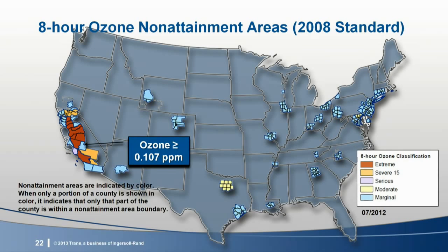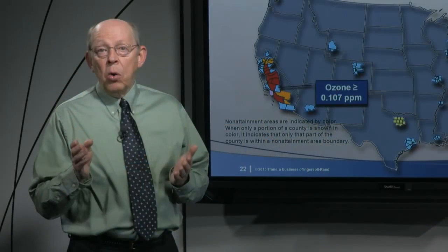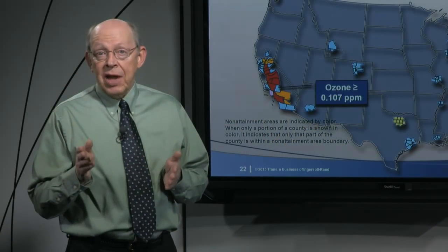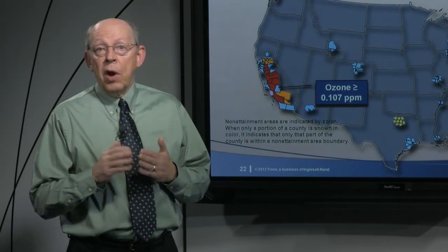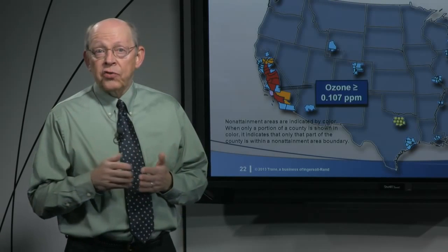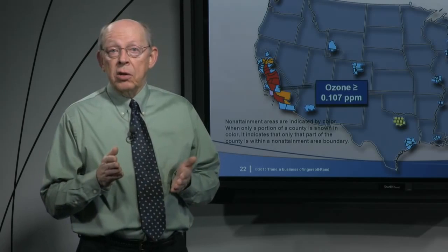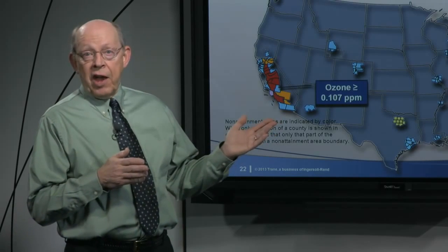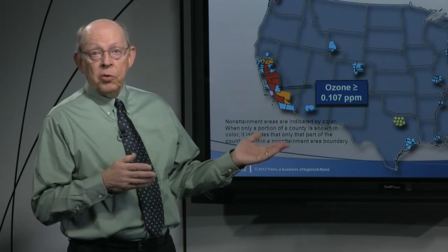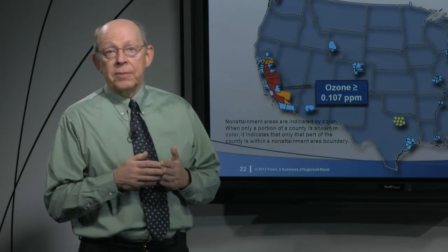Ozone non-attainment areas other than Southern California don't need air cleaners to meet Standard 62, but designers might want to consider using them anyway. After all, breathing ozone is harmful, and besides that, if you're designing a high-performance building, Standard 189.1 requires 40% efficient ozone air cleaners in all ozone non-attainment areas, which includes most of California and many major metropolitan areas throughout the U.S.